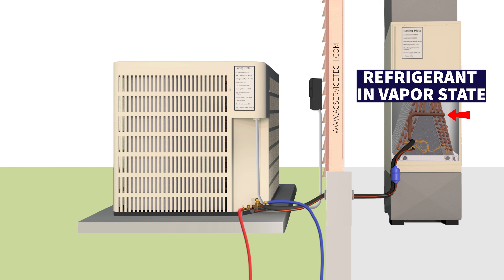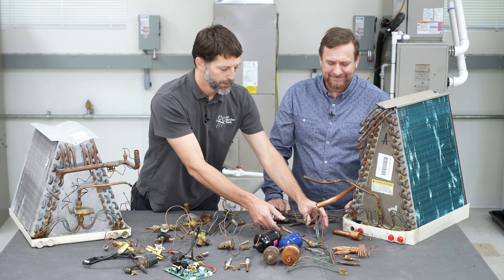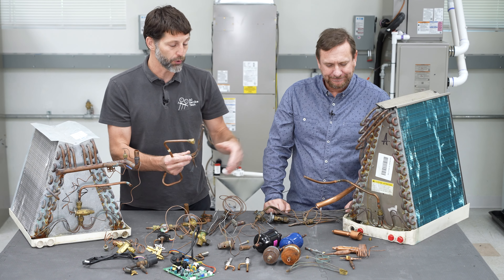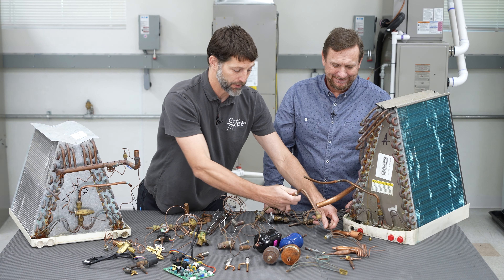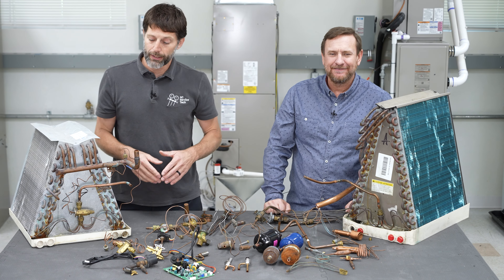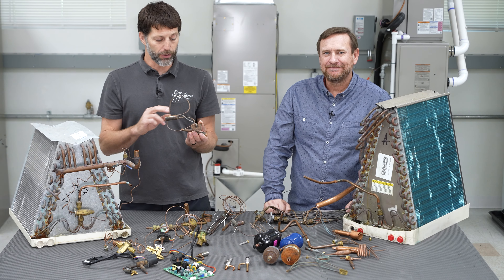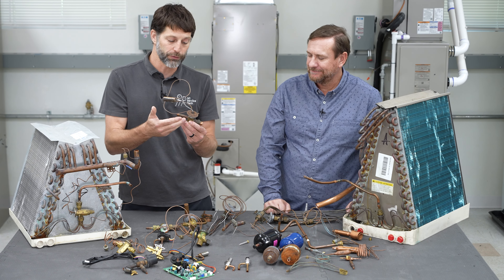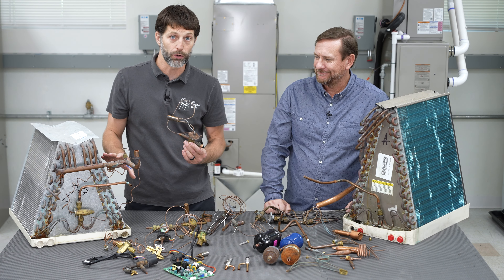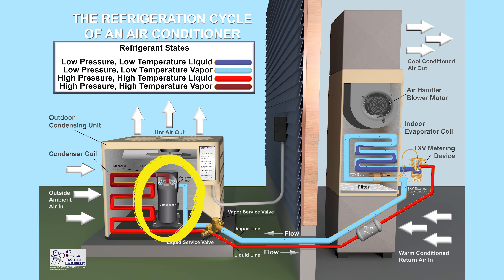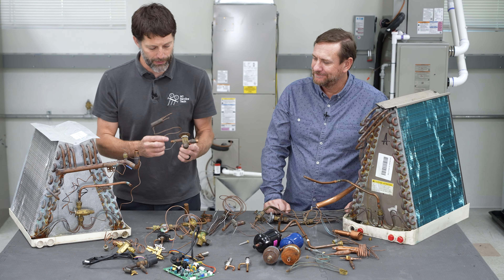After the phase change, the refrigerant is completely in the vapor state and travels out through this pipe to the outdoor unit. A fixed orifice isn't really adjusting the amount of refrigerant into the indoor coil when you have a changing heat load. So if you have a very hot and humid home and want the system to work efficiently, a thermostatic expansion valve is a much better choice. In a dry climate, a TXV will also meter the amount of refrigerant entering the coil so that you don't have liquid heading back to the outdoor unit and into the compressor — remember, it's a vapor compressor and liquid will damage it.